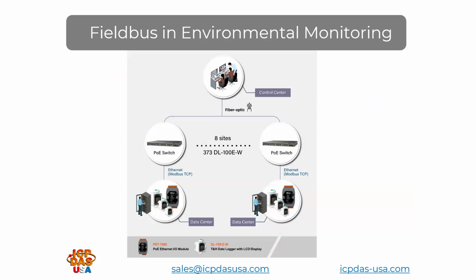The DL100EW remote temperature and humidity data loggers measure the temperature, humidity, luminescence, and dew point of the environment. The data logger supports Modbus TCP and MQTT, enabling it to send temperature and humidity data to the SCADA system in the control center. Besides, the DL100EW only requires one Ethernet cable for data transmission and power supply. This saves on wiring efforts and installation costs and reduces maintenance costs over time, an advantage of PoE, Power over Ethernet.